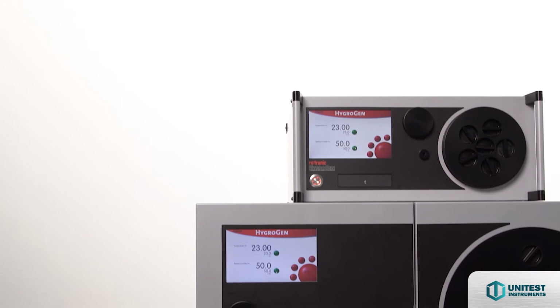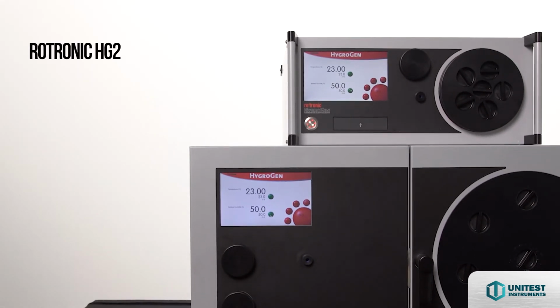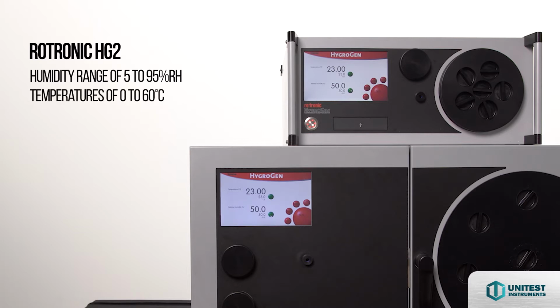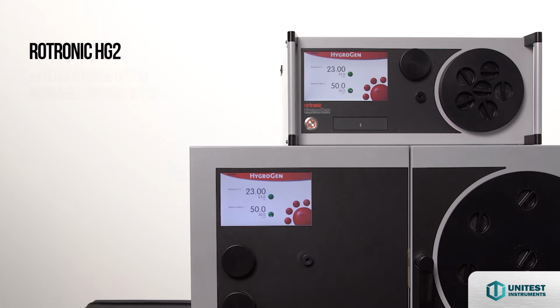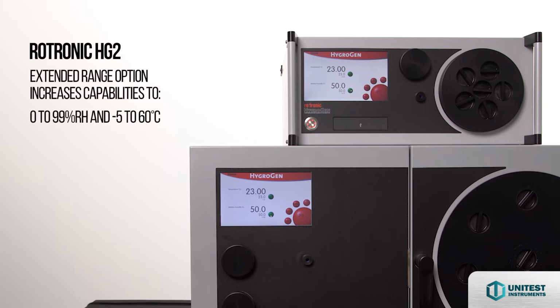The Rotronic HygroGen2 is able to generate humidity range of 5 to 95% RH and temperatures of 0 to 60 degrees Celsius. An extended range option is available, which increases the capabilities of the HG2 to 0 to 99% RH and -5 to 60 degrees Celsius.